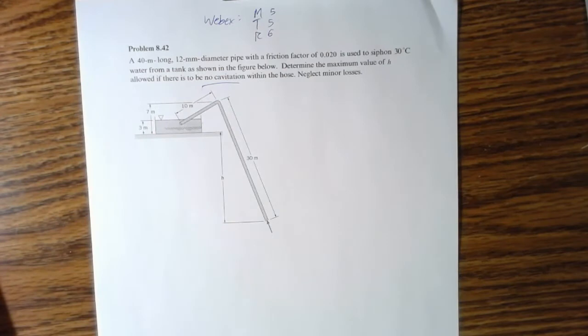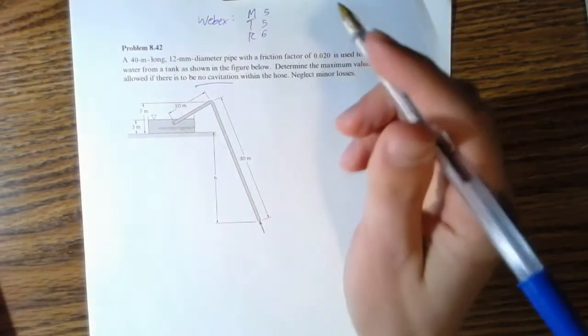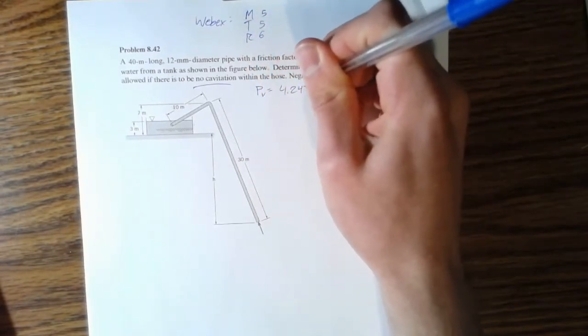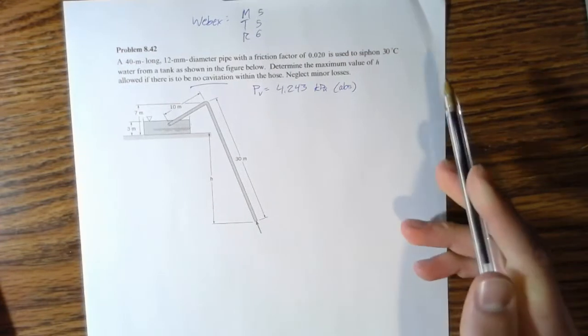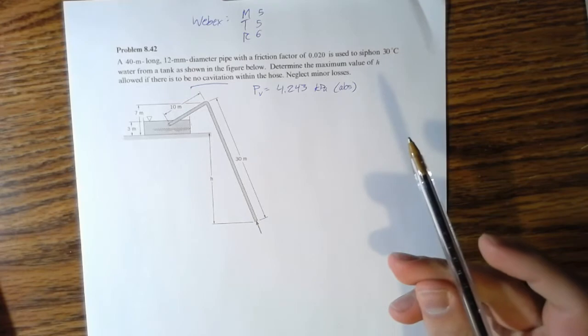I'm not sure if you guys remember cavitation or not, but the idea is the minimum pressure has to be above the vapor pressure. Vapor pressure for water is 4.243 kilopascals absolute.